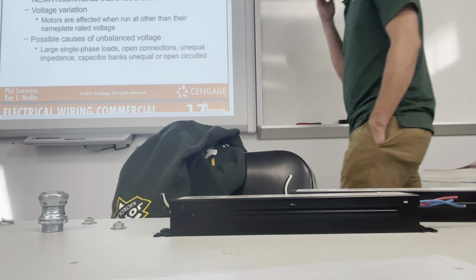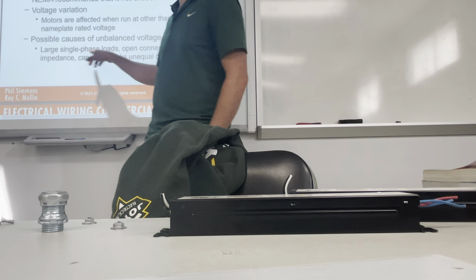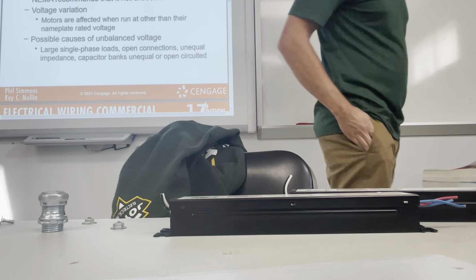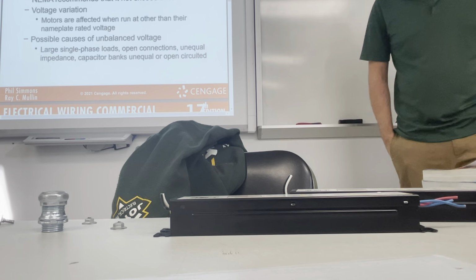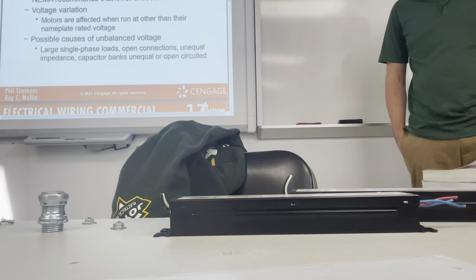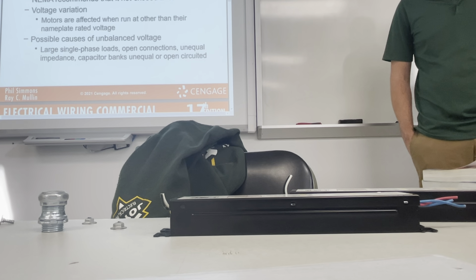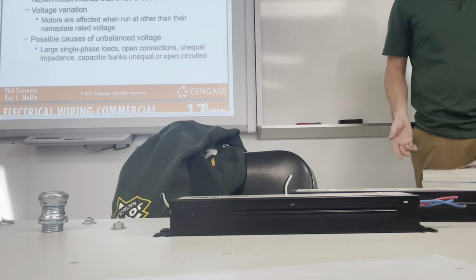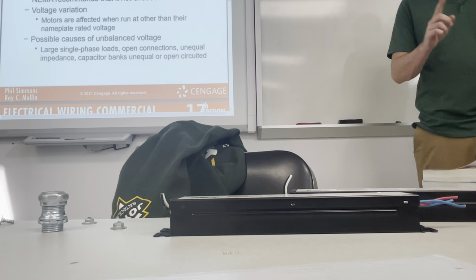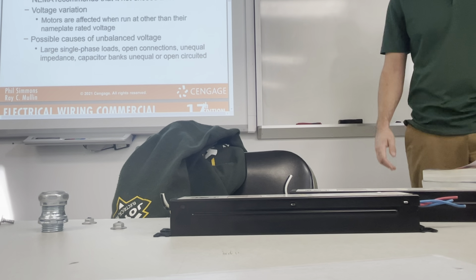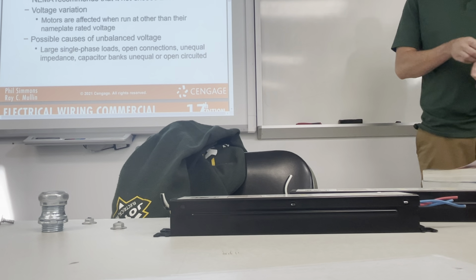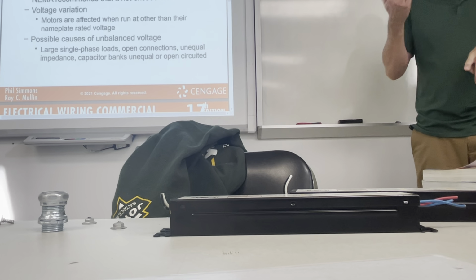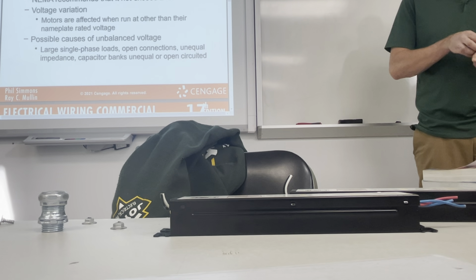Yeah, what they mean by that, and that's normally the biggest cause, is large single-phase loads. That's why you really want to balance out a panel box. You know what I mean? Like when I keep on saying, especially the residential ones, put your biggest loads on top. How many times have you heard me say that? Like your range, your dryer, throw the biggest loads on top. Really spread it out, make it even. When people do three-phase panel boxes, they get confused, or it's rookies.